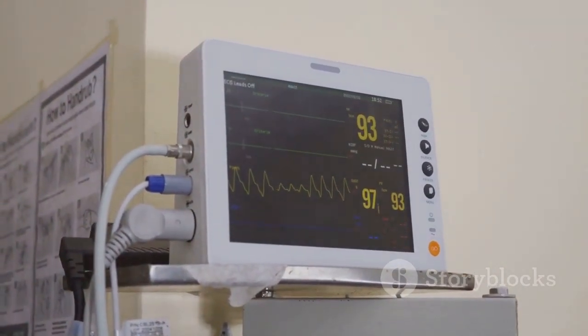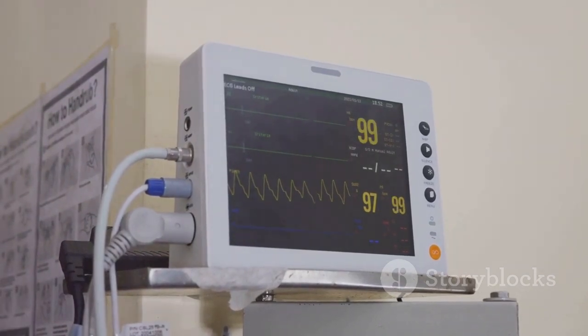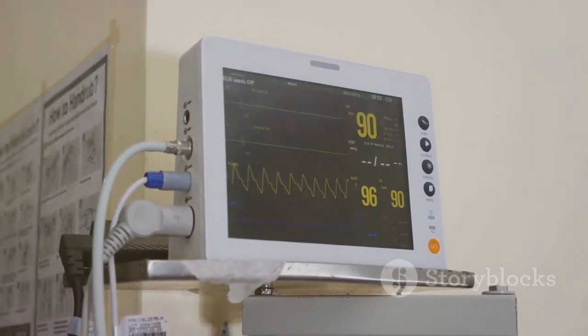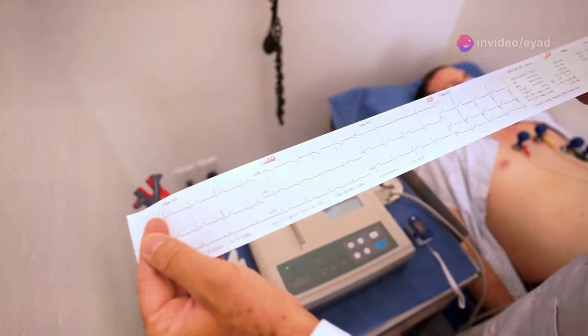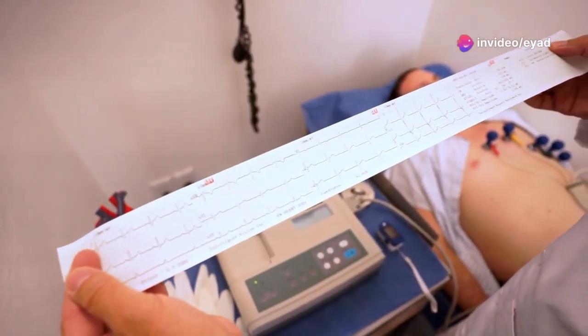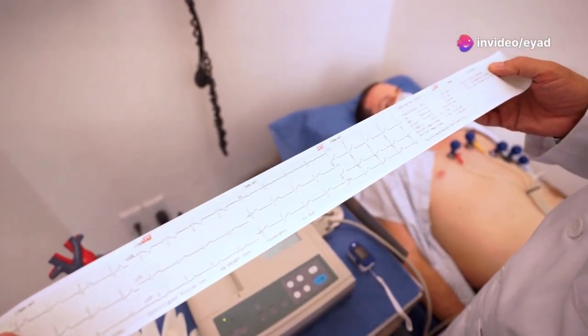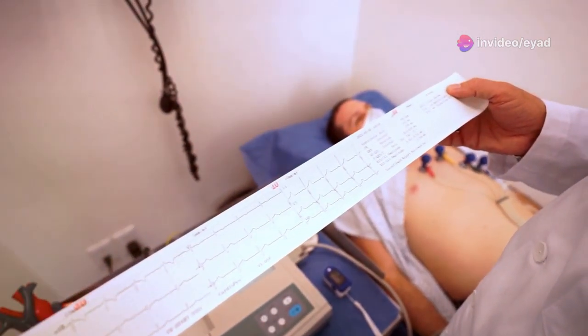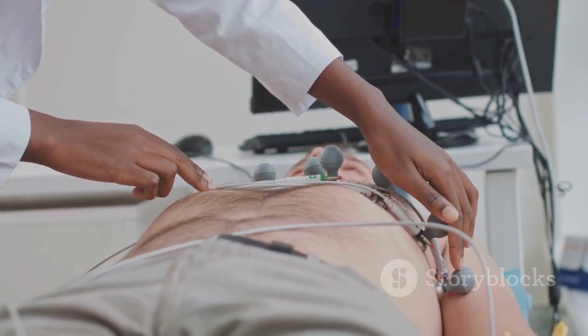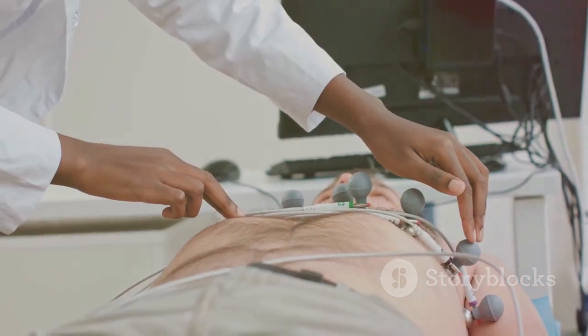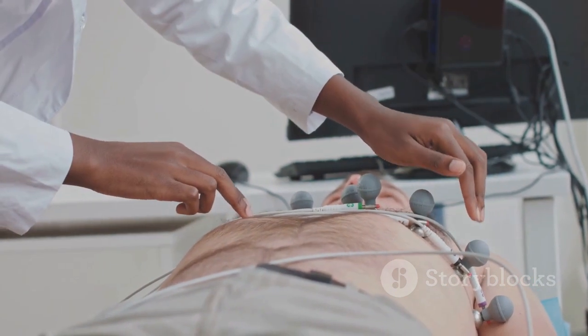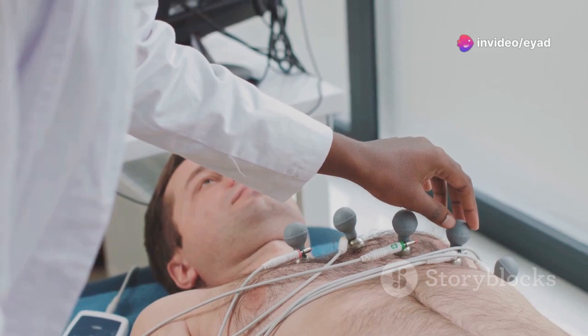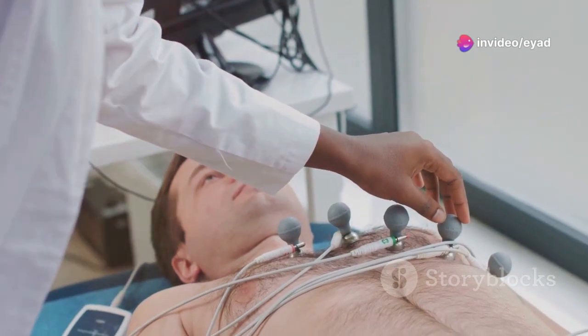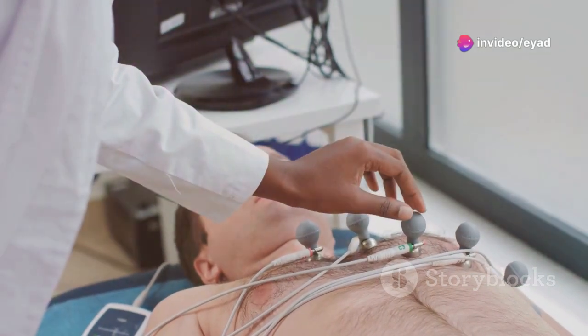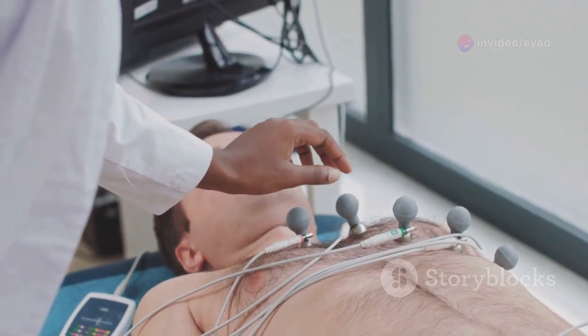Calibration curves ensure that the ECG machine's amplifiers and filters are working correctly, and that the recorded signals accurately reflect the heart's electrical activity. This accuracy is vital for diagnosing and treating heart conditions effectively. Regular calibration of ECG machines is crucial for obtaining reliable diagnoses and making life-saving treatment decisions. Without regular calibration, the risk of misdiagnosis increases, potentially leading to inappropriate or delayed treatment.